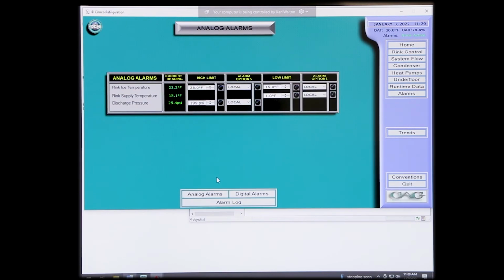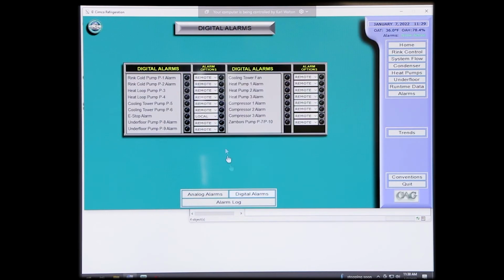Alarms. There's actually 3 pages here. Okay, so if there is an alarm, you'll see a red button here. If it's not in the analog alarms, it could be in the digital alarms. You'll see it here. Okay? If one of those pieces of equipment, if somebody's gone downstairs and hit that e-stop alarm, you're going to see that lit up. Somebody hit that switch. You'll see it there. Okay?